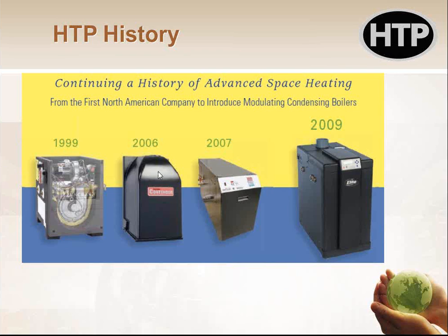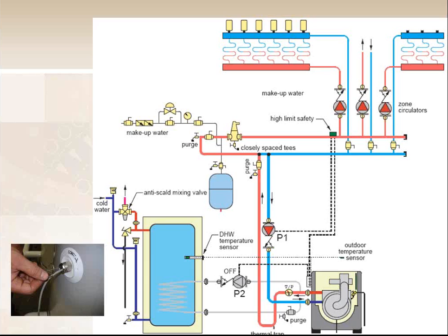In 2006, they came out with a little wall-hung version called the Contender. 2007, the bigger commercial sizes, which now go up to 1.7 million BTUs. And then in 2009, they retired the Munchkin and brought out the Elite line to get a little more efficient and to enhance some of the things that people didn't like about the Munchkin one. So those are low mass boilers, and this is a typical piping schematic for a low mass boiler plant.